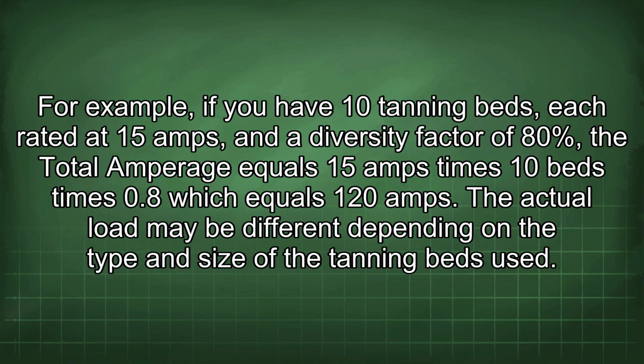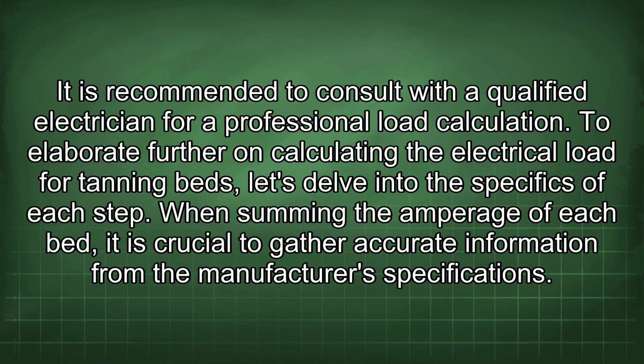For example, if you have 10 tanning beds, each rated at 15 amps, and a diversity factor of 80%, the total amperage equals 15 amps times 10 beds times 0.8, which equals 120 amps. The actual load may be different depending on the type and size of the tanning beds used. It is recommended to consult with a qualified electrician for a professional load calculation.